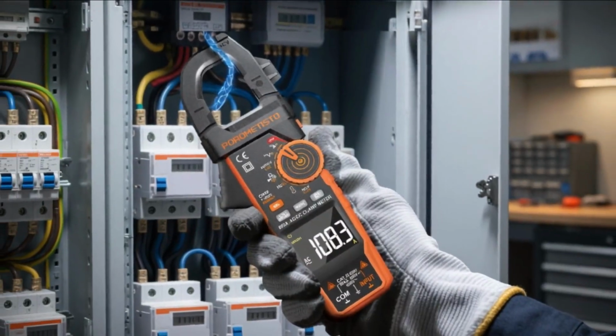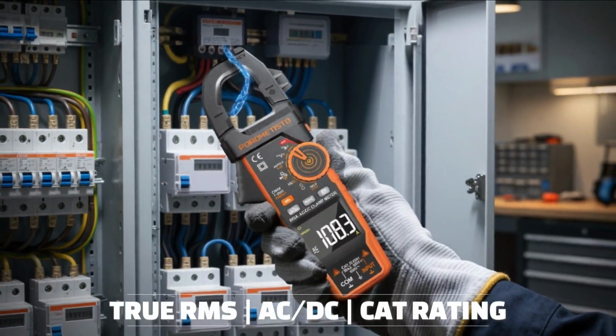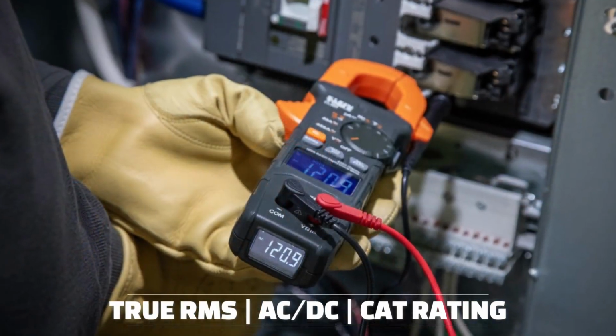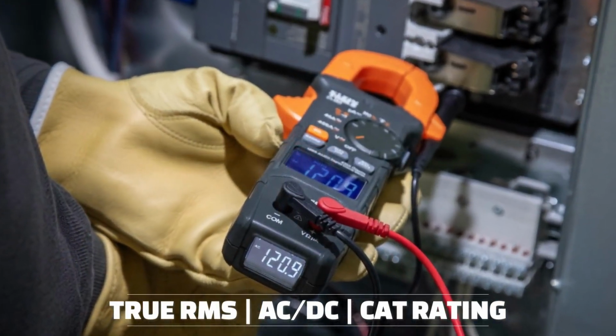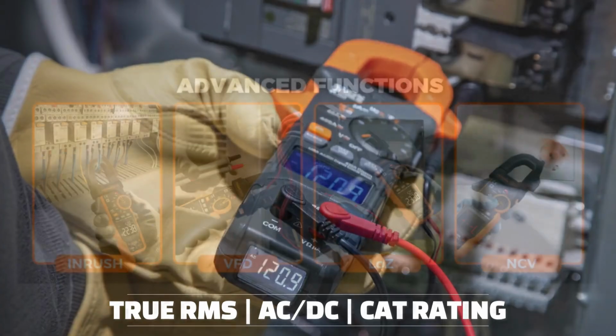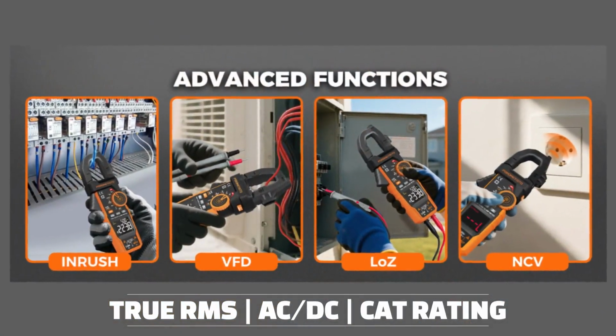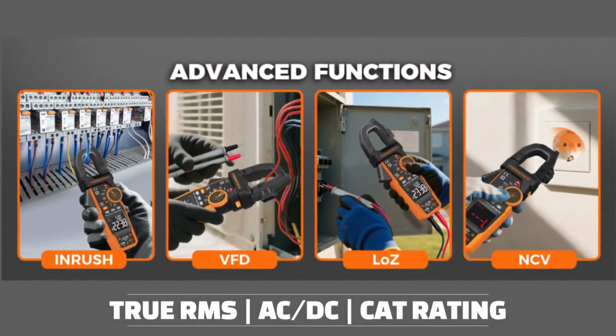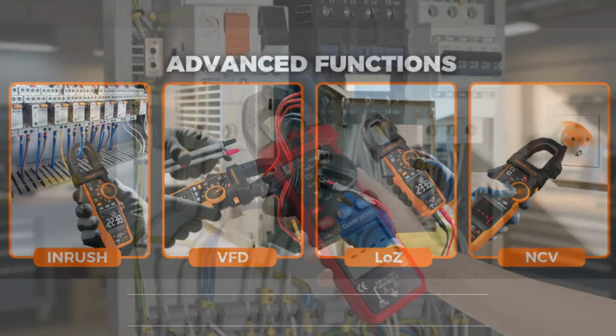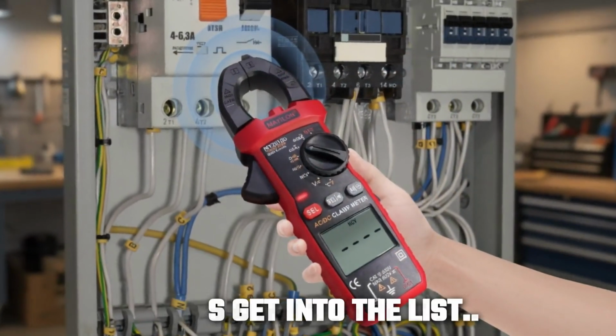Before choosing a digital clamp meter, check its True RMS capability, AC and DC current range, CAT safety rating, jaw size, and specialized features such as inrush capture, VFD filtering, or LOZ mode. Now let's get into the list.